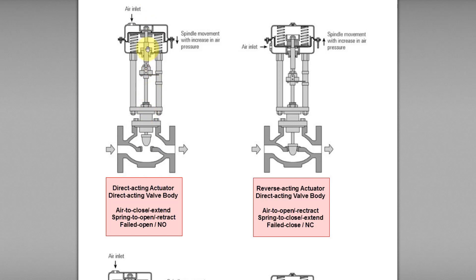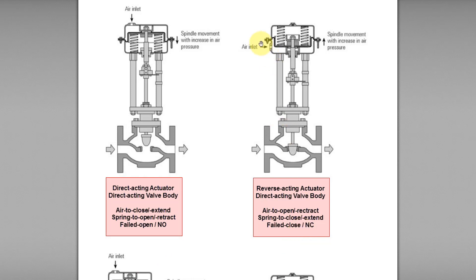Similarly, this case is called air-to-open or air-to-retract control valve because when air is applied to the lower portion of the actuator, it pushes the diaphragm and spring outward, causing the shaft or stem to retract outward and open the valve body. It is also called spring to close, spring to extend, or fail-closed, because when the air is cut off, the spring bounces downward, the stem extends downward, and closes the valve.